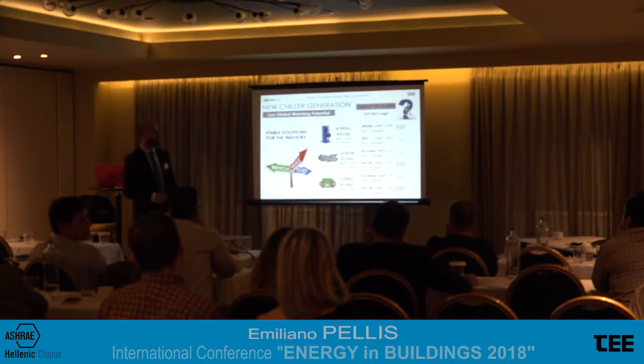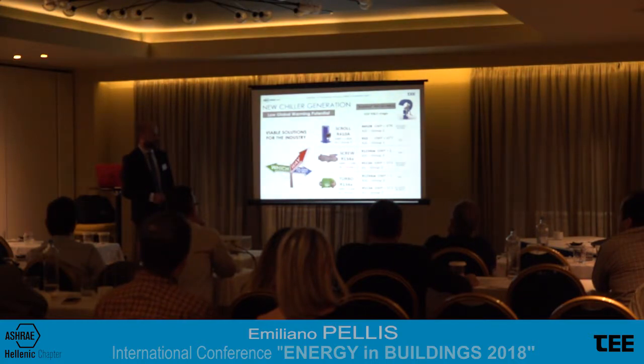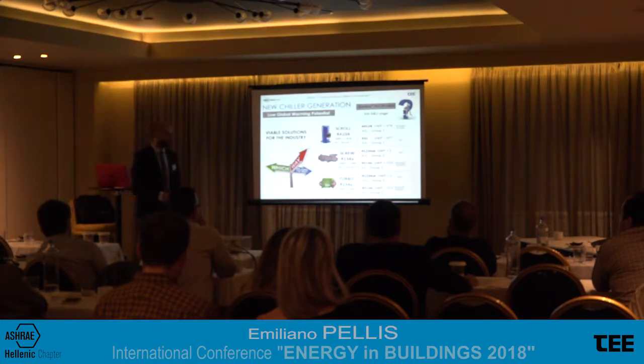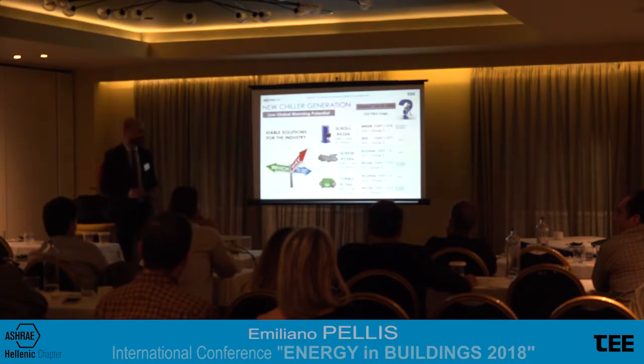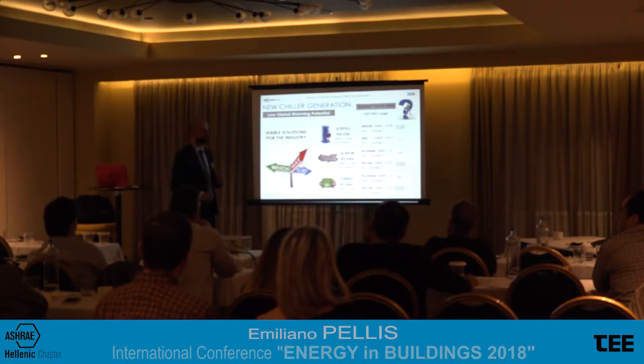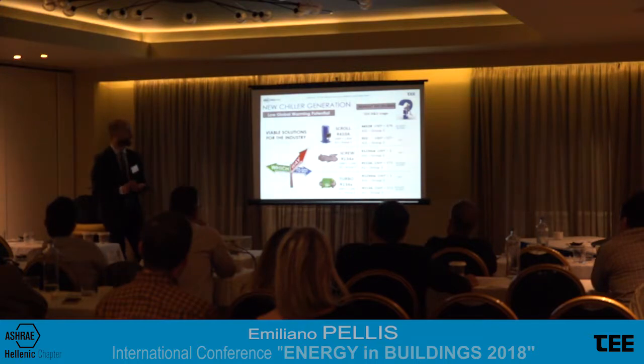What about the new possible alternatives? They are the same for the turbo and for the screw, so let's look here. We have two good options. One is 513A, which is a medium GWP refrigerant, around 600, so lower than this. A1 class, so again not flammable, and again group 2 of the PED directive. This is a good refrigerant because it is not flammable, so it can be handled exactly as the 134a, and there is a medium GWP, so a reduction in GWP, and also a very limited impact in terms of performance, in terms of cooling capacity and efficiency for the chillers.